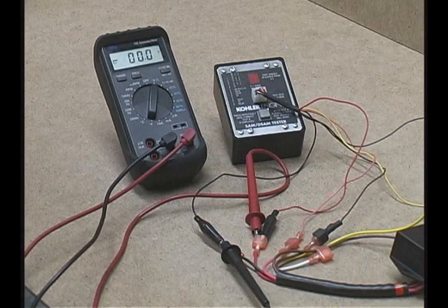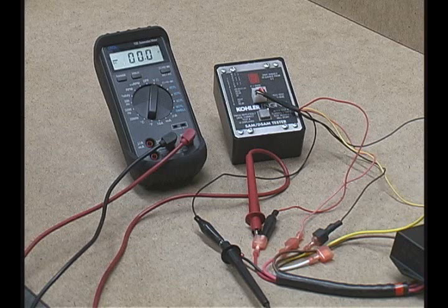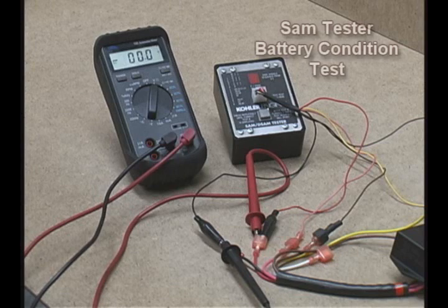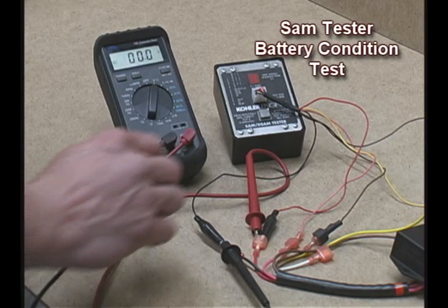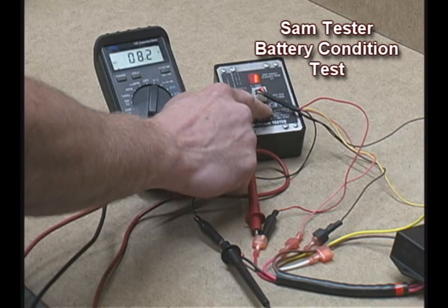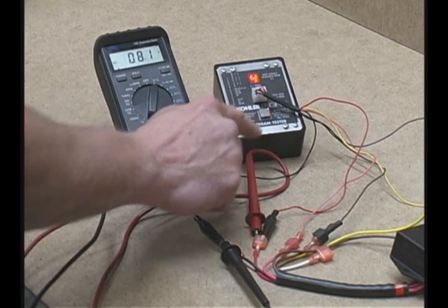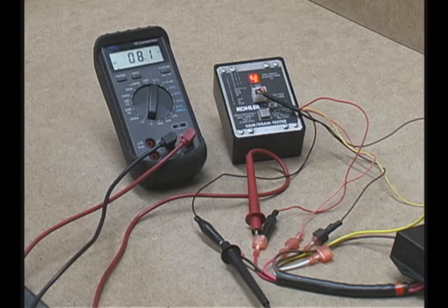The SAM tester is powered by a 9-volt battery. Most SAMs are designed to operate to a minimum of 7.25 volts. Incorrect test readings will result if the tester battery drops below 7.25 volts. To periodically test the battery, connect a DC voltmeter between the red and black lead wires while the tester is connected to a SAM. Start the appropriate test sequence and monitor the voltmeter reading. Replace the 9-volt extended life alkaline battery if the voltage drops below 7.25 volts at any time during the cycle.